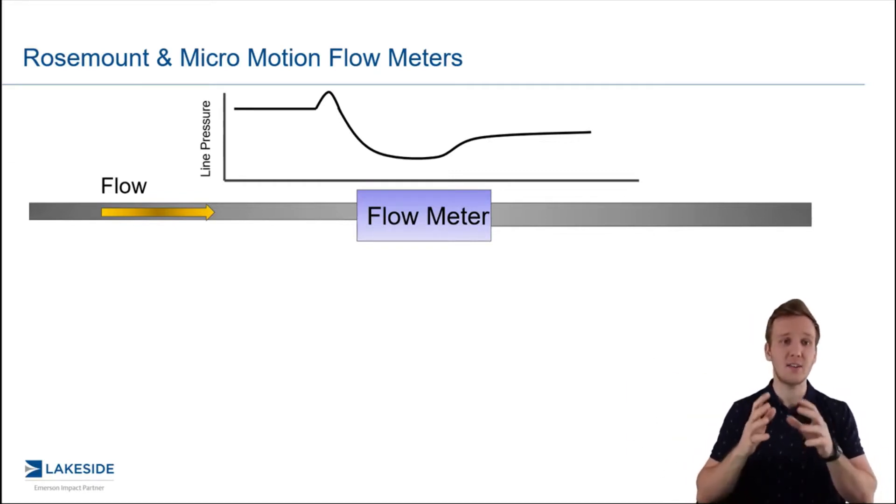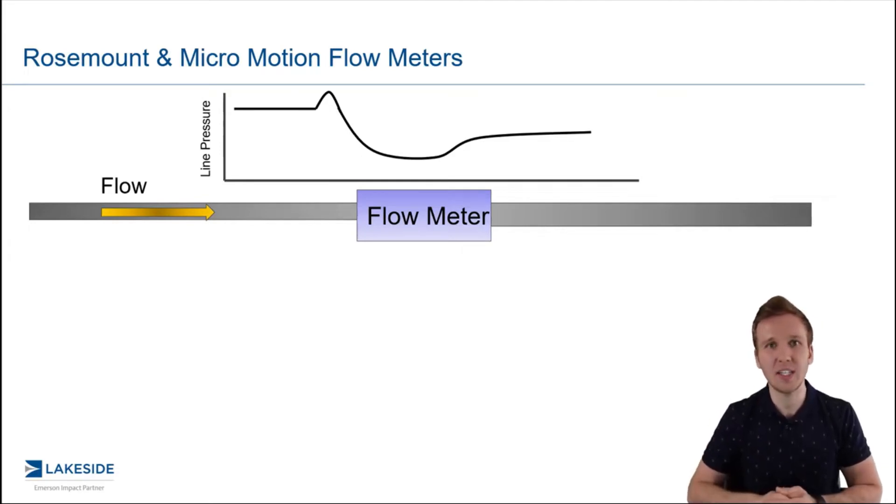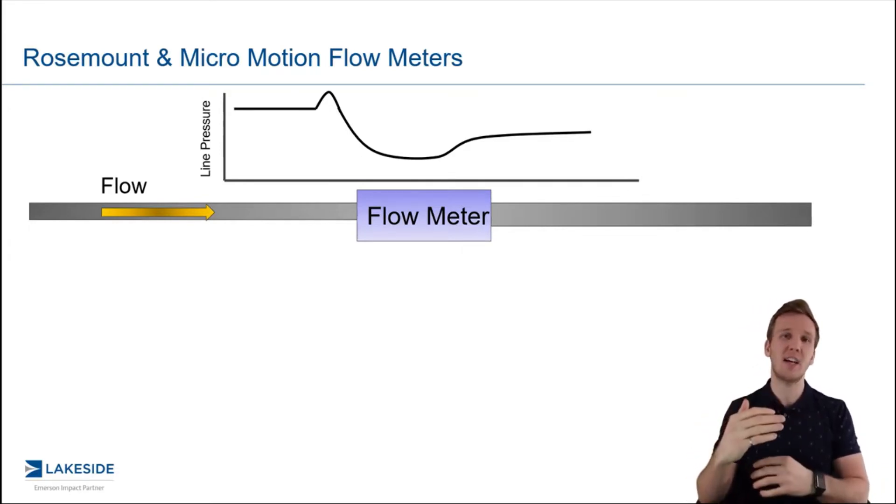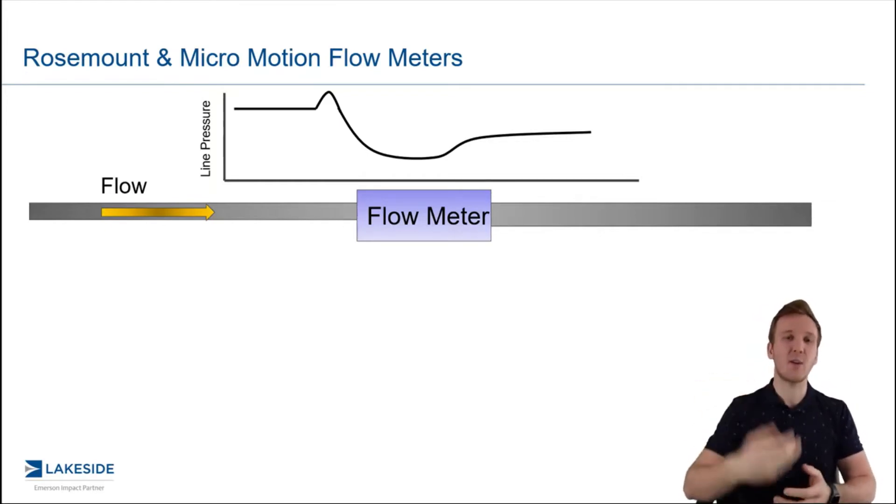Now, as you can see, there's a specific line pressure beforehand, say it's 100 PSI, and then right before that flow meter, we actually have a slight uptick, a slight increase, and that's because the flow meter typically restricts the cross-sectional area. So you kind of have that buildup, if you will, of product that increases that pressure.